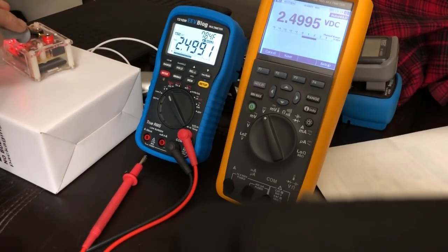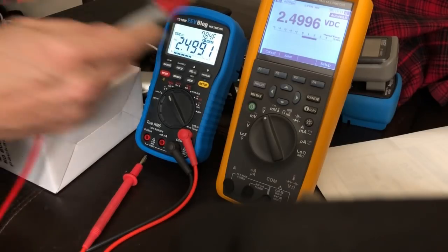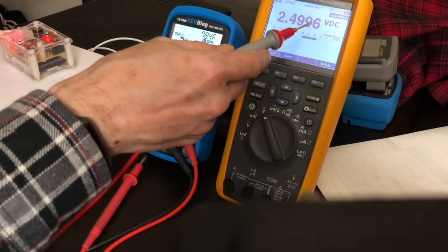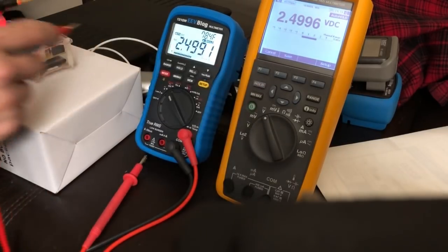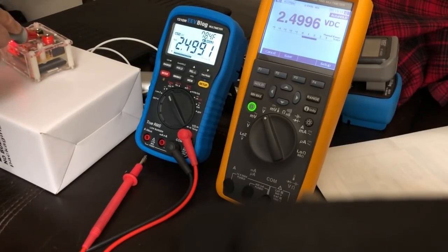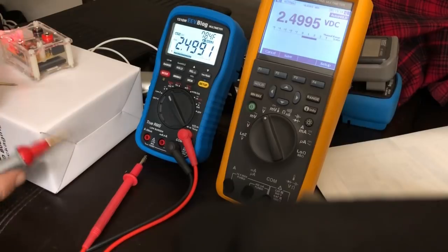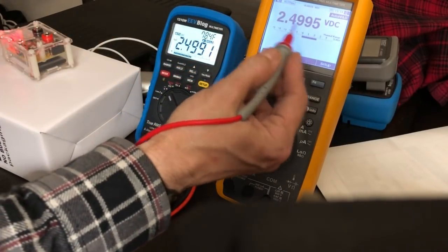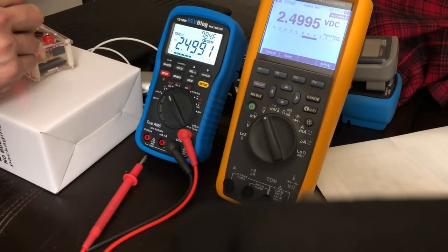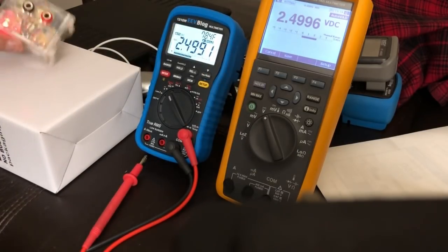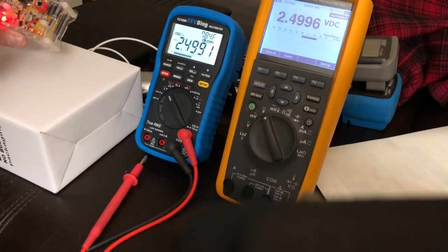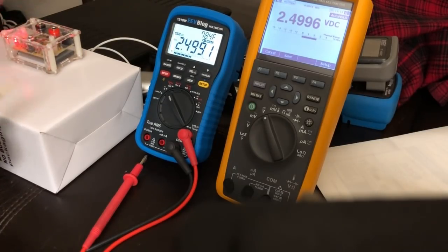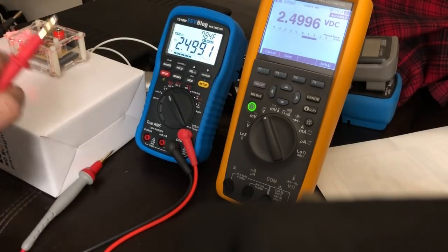You gotta do that super quick or something. Now, 24996 - this could be 1 microvolt off, and it will detect the change. See? It just changed to 5. So this is what I expect from an actual auto hold feature with a meter of this type of resolution. Even 1 microvolt, it should calculate. There it goes, it just changed to the 6, which is the drift that I expect from this particular voltage reference. So that I expect.